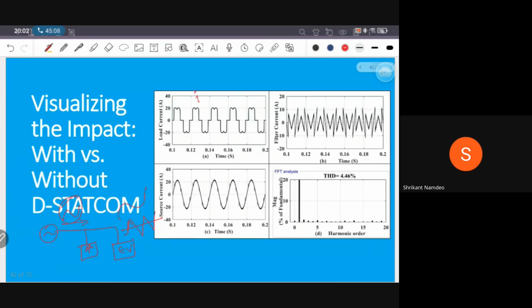Here you can see this is the load current, let me represent it as IL, and this is the current supplied by the D-STATCOM. When we see this current, we won't feel pleasant because this is an annoying one. But when we see the result here, we can see we have reduced the ripples and generated an almost sinusoidal waveform, and we achieved THD of around 4.46%. This fits well within the IEEE 519 standard.